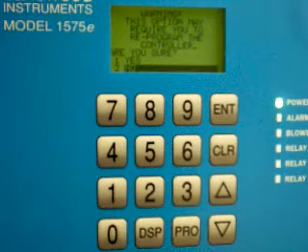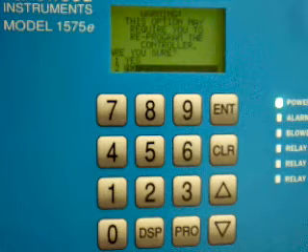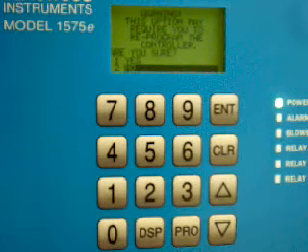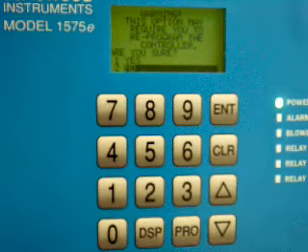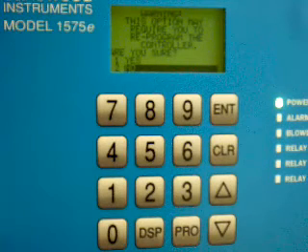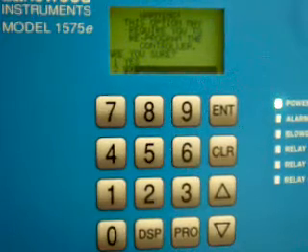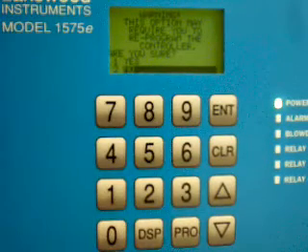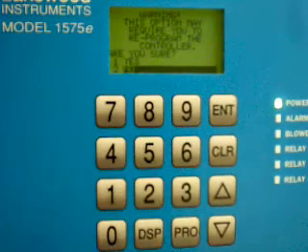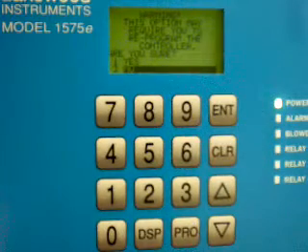Your calibration levels, all your set points, any sort of relay configuration. This takes it back to the bare bones factory default looking for all information to be re-input, including water meter types, the gallons feed, the whole thing.